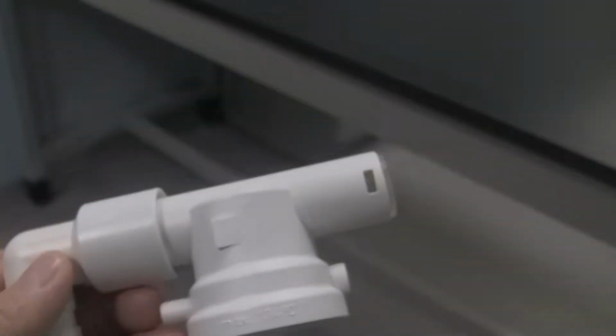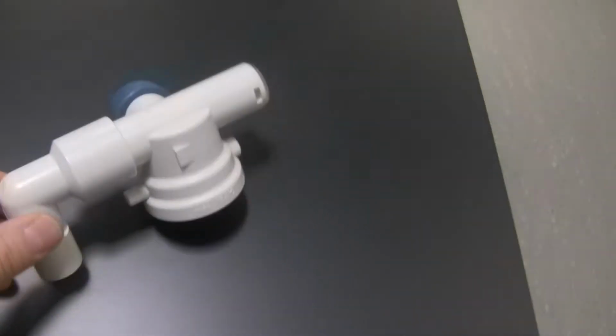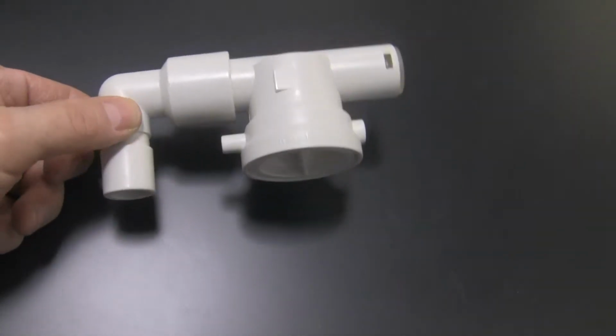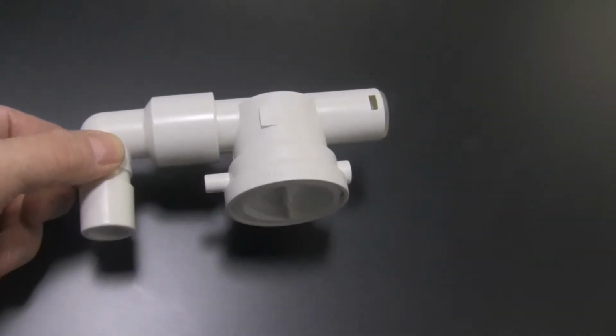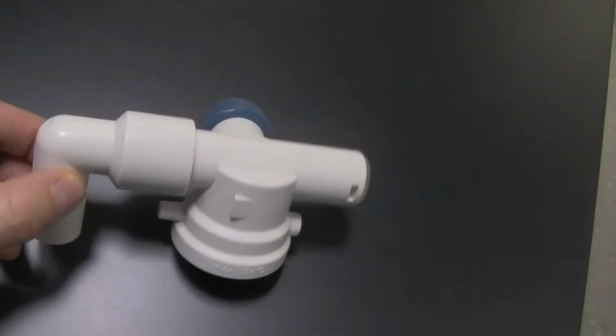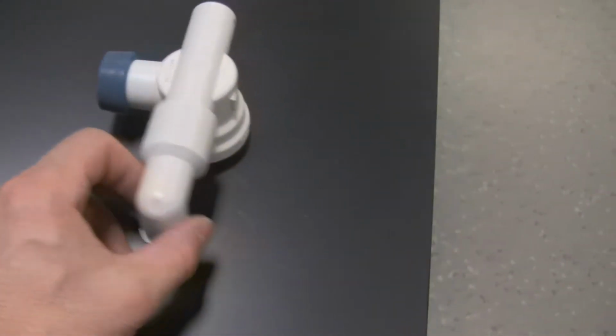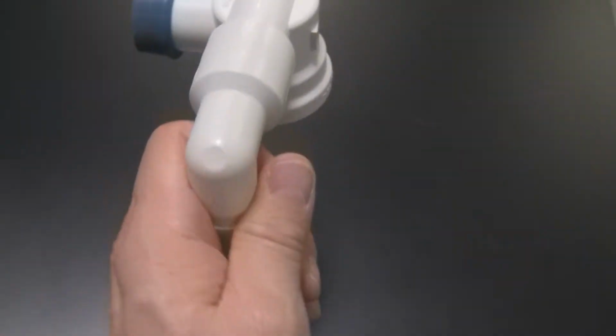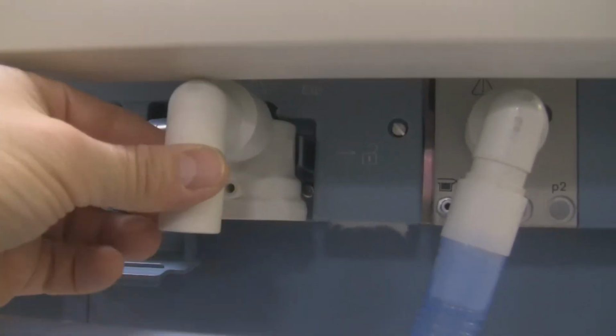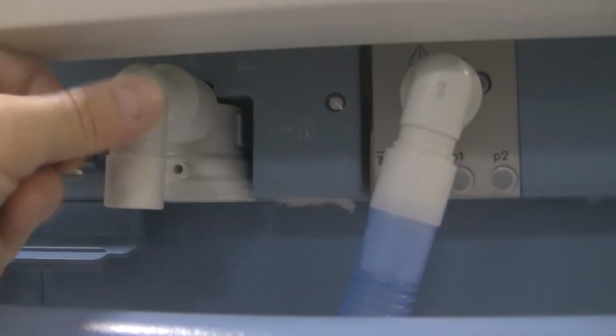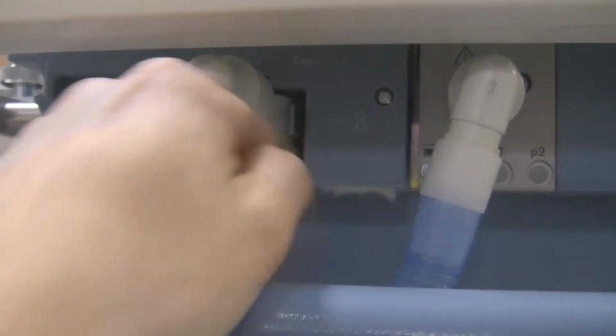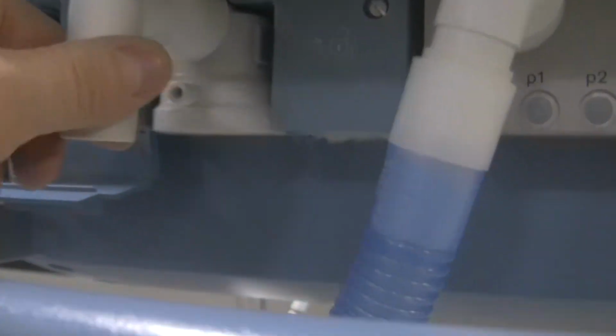So this is the exhalation block right over here, or the exhalation manifold. This would be sent out for cleaning between patient use as well. Okay? Now to place this in, simply hold it like this, go back to your ventilator, line it up here, and continue to push it in until you hear the click. When you hear that click, this locking mechanism locks this in place, so it's good to go, it's in there fairly securely.